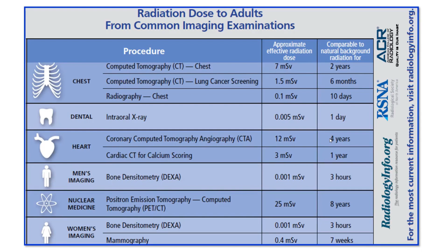So for every investigation, most hospitals have a set protocol in order to meet the effective radiation dose. If you are exceeding this, case to case, you should have reasons for exceeding it, and also which staff is exceeding it. If somebody is not following it and exceeding the radiation, then you have to give them proper training, provided the machine is calibrated at given intervals. There should not be any malfunctioning of the machines, so you have to monitor.